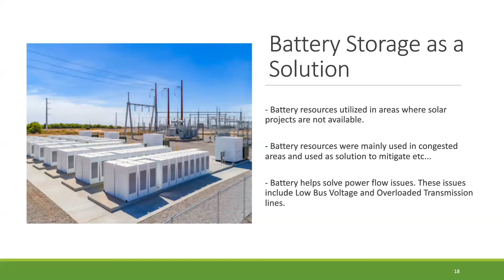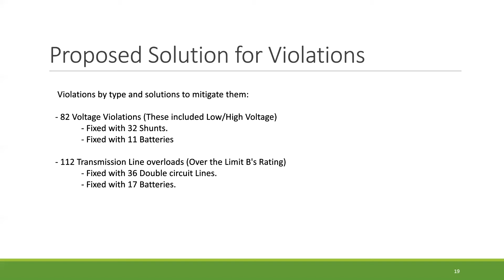And so as previously mentioned, the contingency analysis is a tool in the PowerWorld Simulator for analyzing steady state in our system. The contingency analysis will then create a list of types of violations at a certain location. Therefore, here's the list that we have for the number of violations and the solutions to mitigate them. And so we ended up having 82 voltage violations, which were fixed with 32 shunts and were also fixed with 11 batteries. And we ended up having 112 transmission line overloads, and those were fixed with 36 double circuit lines and were also fixed with 17 batteries. And now I hand it down to Michael to present the transient analysis.